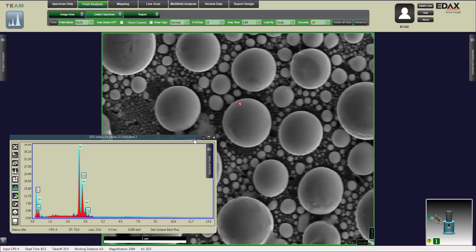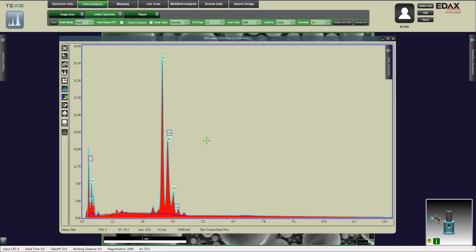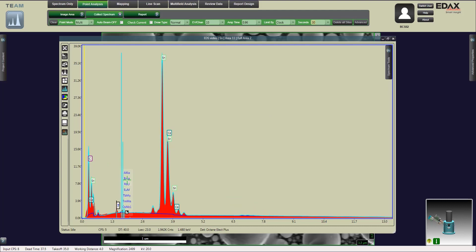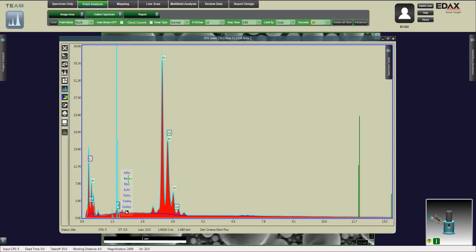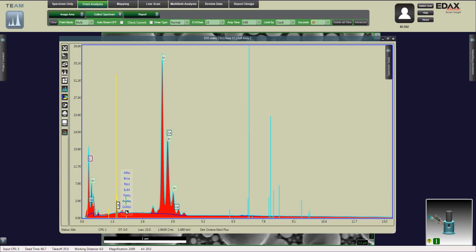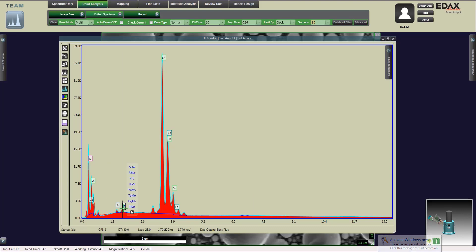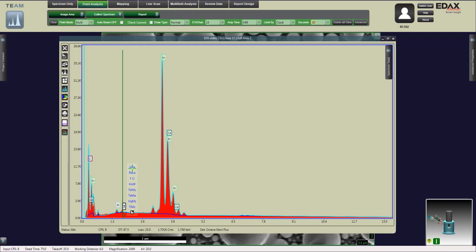Alright, now we have a completed scan. We want to check for peaks and check the background also. We notice we have a dark blue line, which is our background. We have a light blue line, which is the sum of all the peaks. If any peaks are above that light blue line, then it hasn't been identified yet. We can click on the peak, hover over the question mark, and select the elements that we want to fit. Scrolling down through that list, you can see where the peaks shift. That is an aluminum peak that we have there.